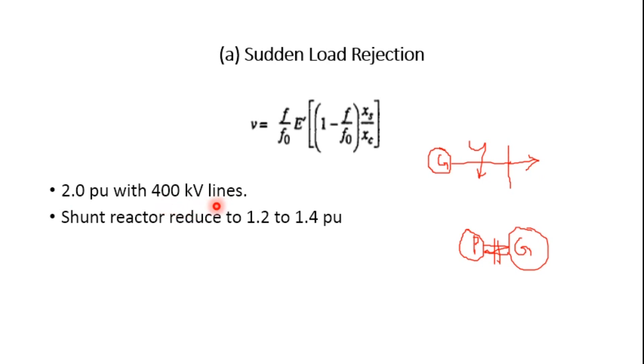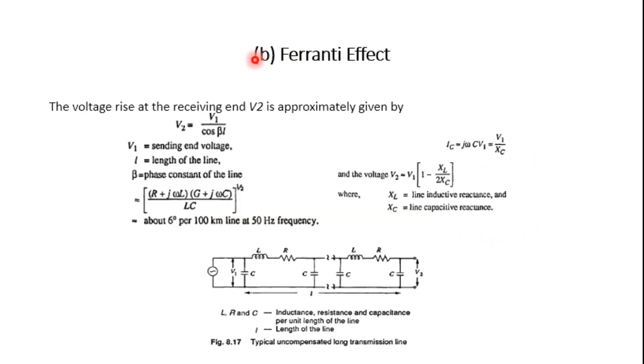The voltage at the sending end is affected by the line length, the short circuit MVA at the sending end bus, and the reactive power generation of the line, considering both line capacitive reactance and shunt or series capacitors together. Hence this shunt reactance reduces the overvoltage to 1.2 to 1.4 times the rated value.